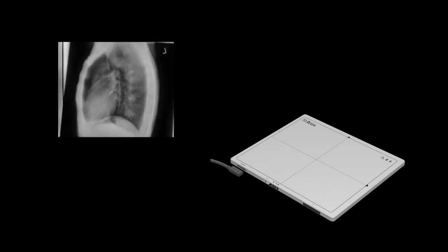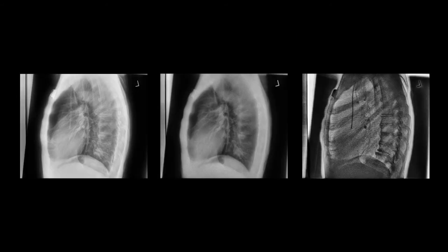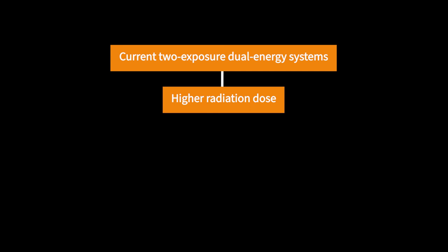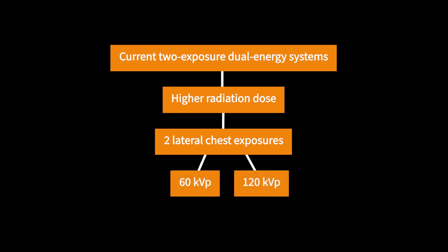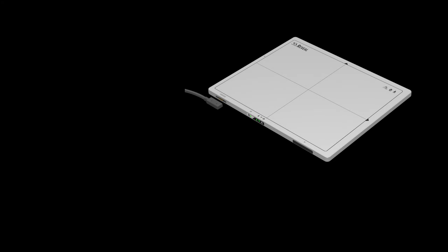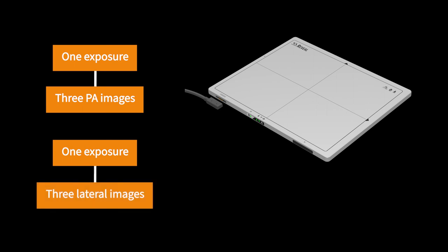This case also highlights how the KA Imaging Reveal device enables the discovery of masses using lateral dual energy chest x-ray images. Lateral dual energy x-rays are not commonly obtainable using current two-exposure dual energy systems, because the patient would receive considerably higher radiation if two lateral chest exposures — one at 60 kVp and another at 120 kVp — are given. For the reveal device, all six images were generated using only one exposure to obtain three PA images and only one exposure to obtain three lateral images, both performed at 120 kVp, typical for chest x-rays.